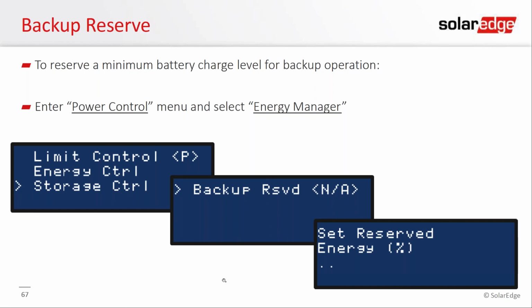Yes. So let's say you drain your battery below the threshold, and you say, okay, my battery is completely dead. When the sun comes up, the inverter is going to try to start powering those loads that you have that are still on. And if they're still on, the inverter is going to trip off and say, nope, I don't have enough energy to power the consumed loads. So if you turn off those loads, then the excess energy just starts dumping into the battery, which is great. So you start charging the battery, and then when you have enough energy in the battery, you turn the loads back on, and everything's great.